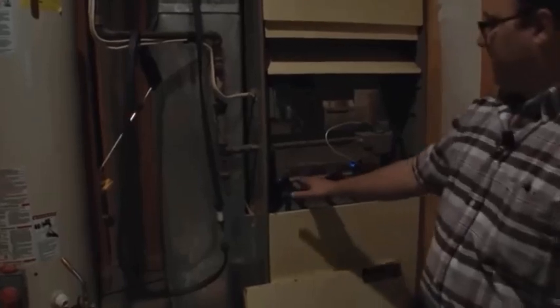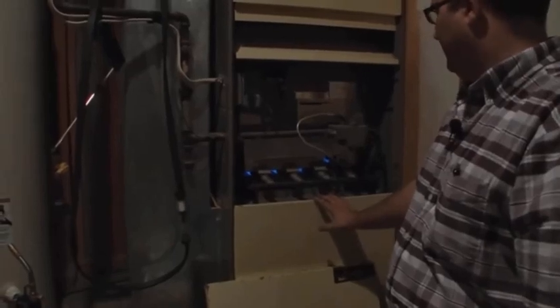These older furnaces don't have any safety devices. The newer furnaces would have like a heat sensor right here and maybe a heat sensor right here, and if they get too hot, they shut the gas off. And flame rollout, if it was substantial, would cause that switch to open and shut the gas off. So there are some safeties these older furnaces don't have, that we really want to make sure that we don't have a lot of flame rollout on these.